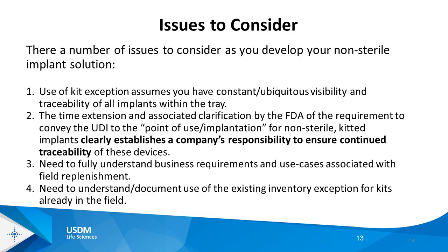But let's just talk about implants. Not all implants can be directly marked, and so there's a series of self-exceptions that can be taken. What the proposed rule didn't do, though, at the time was to speak to, okay, fine, you can't directly mark those devices. How is the UDI of that implant going to be made available?